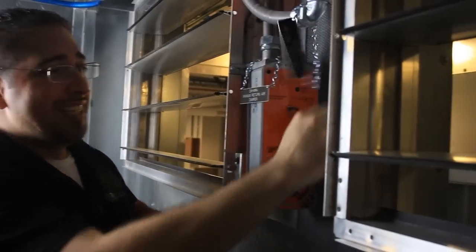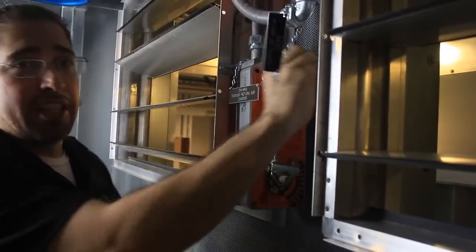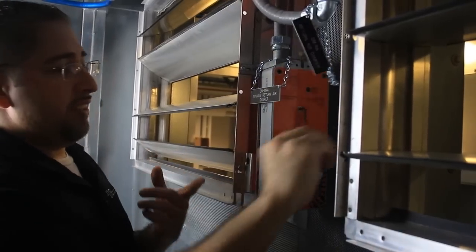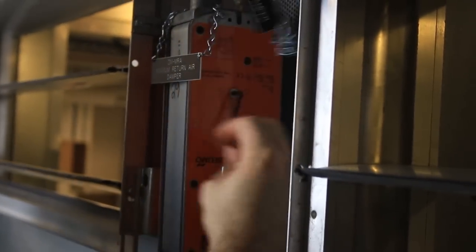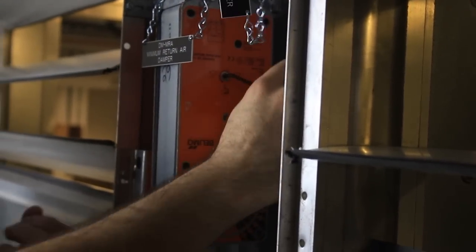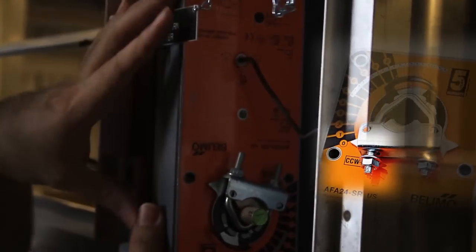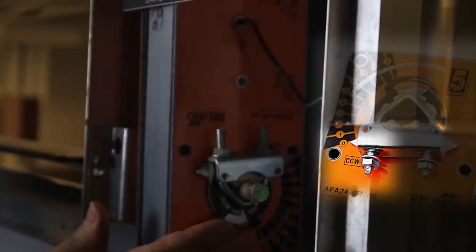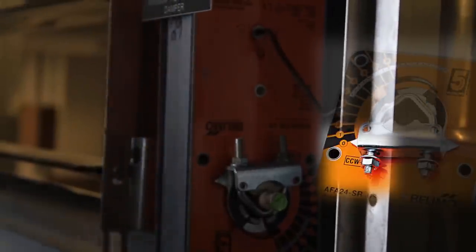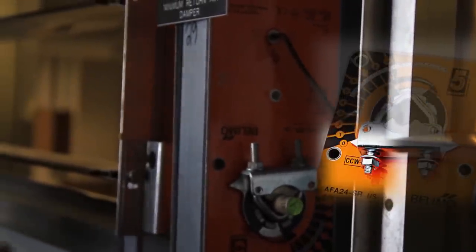Some other things with the spring return is it depends on which way you mount this that you want the spring return. So in this case, I'm actually driving the shaft of this damper, and as you're looking at it, it's going clockwise. If you wanted to rotate the damper counterclockwise, all you have to do is mount this actuator, flip it around, and then stick it right back where it's mounted now. Then at that point, the spring return action would be spinning the shaft counterclockwise.